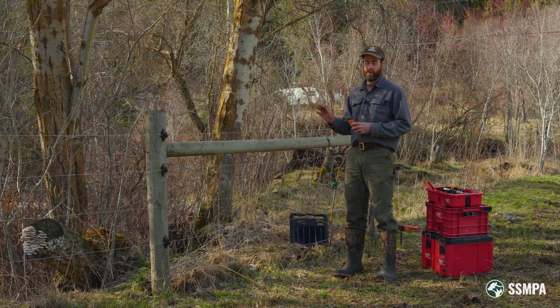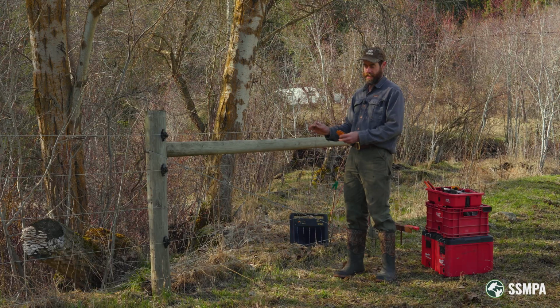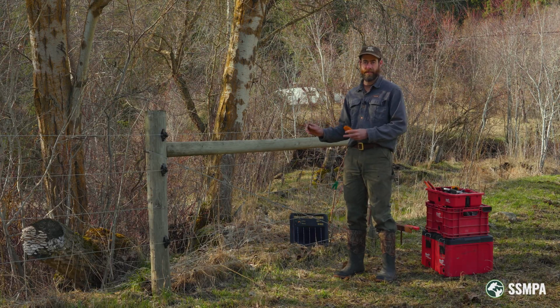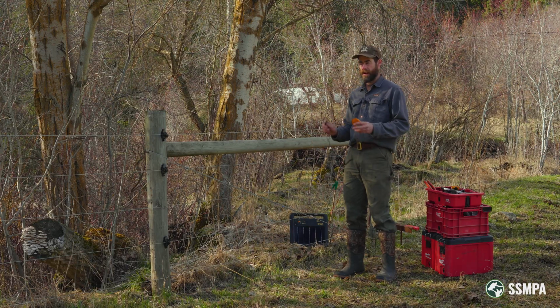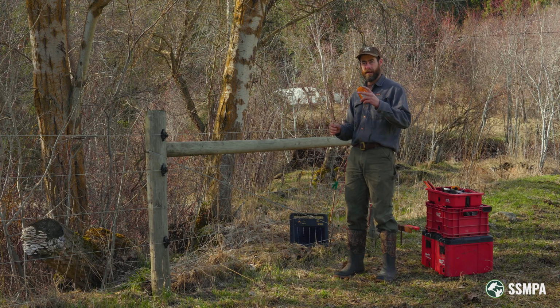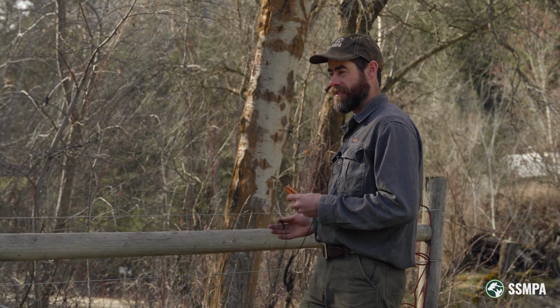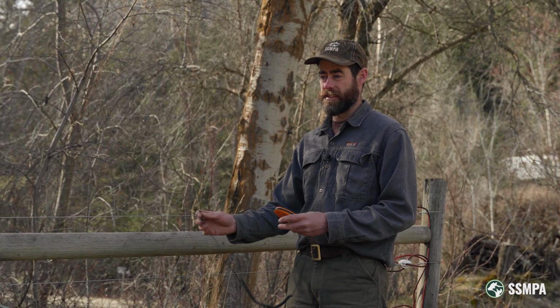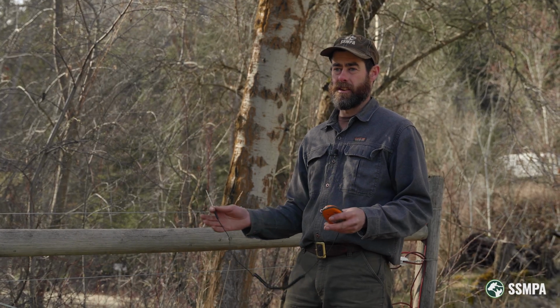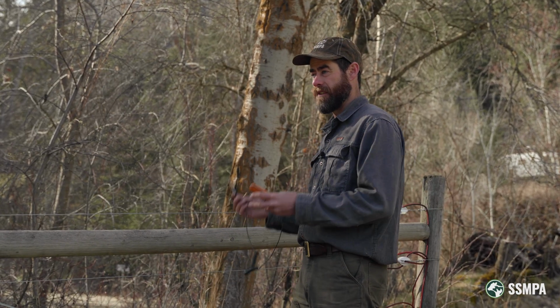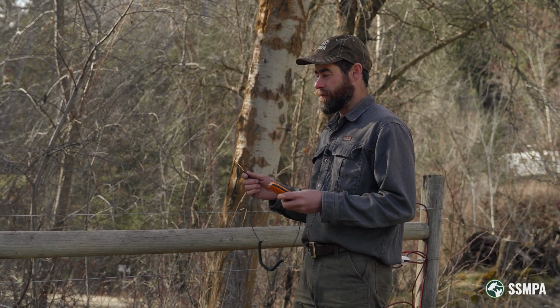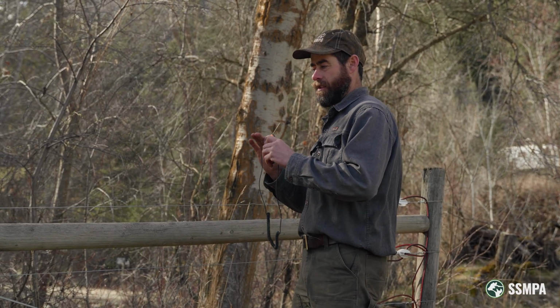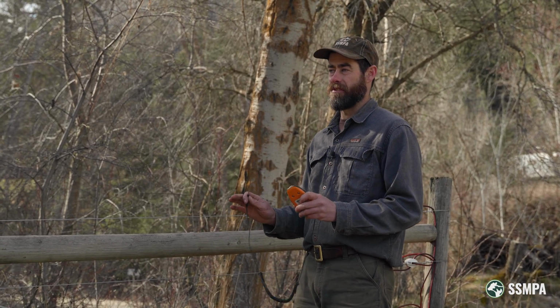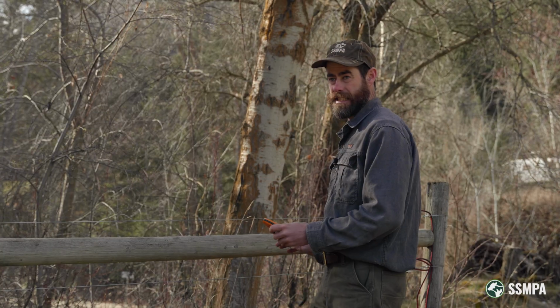The starting point for troubleshooting your fence is understanding your fence's baseline performance. Every fence is going to be different. Every combination of wire, netting, temporary fences, and your Energizer and your grounding system, as well as the conditions on your farm, are all going to influence your fence's performance. So it's important to know when there's no problem, no big fault on the fence, what's the baseline.